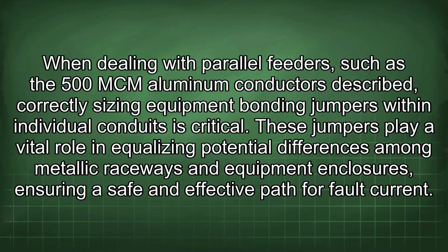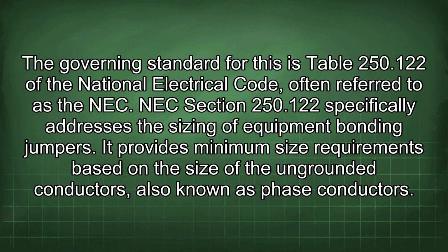When dealing with parallel feeders such as the 500 mcm aluminum conductors described, correctly sizing equipment bonding jumpers within individual conduits is critical. These jumpers play a vital role in equalizing potential differences among metallic raceways and equipment enclosures, ensuring a safe and effective path for fault current. The governing standard for this is Table 250.122 of the National Electrical Code, often referred to as the NEC.